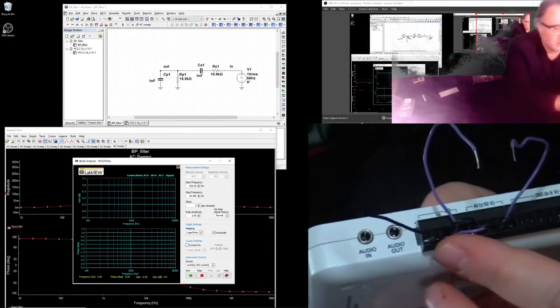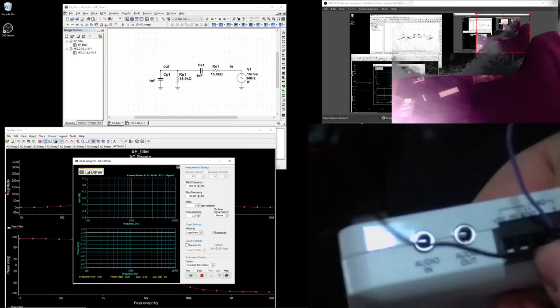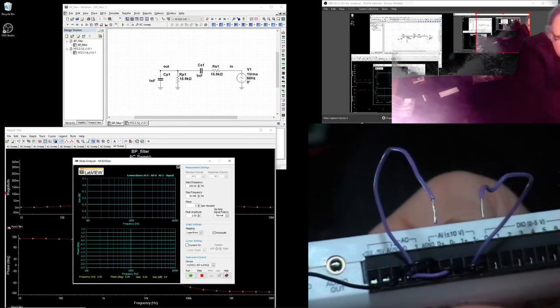So for this reason, what I did is that I defined a common analog ground, which will be this wire, the black wire. And then to this ground here, very locally, I connected the analog ground. Then I connected with a small cable the analog ground of the analog input port here. Then I connected to this the analog input 0 minus. You can see the connections. And then from analog input 0 minus, I connected also the analog input 1 minus. So they are all locally connected.